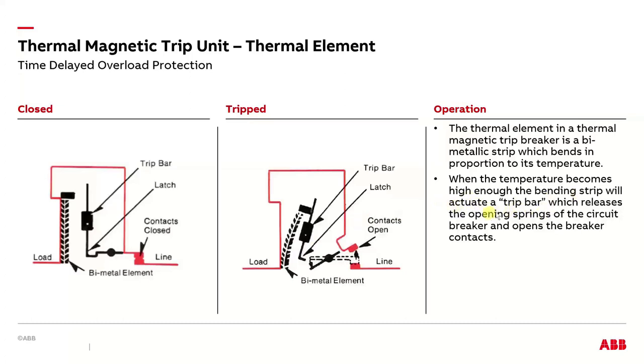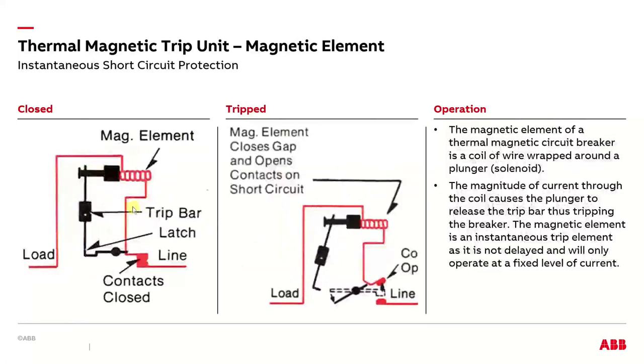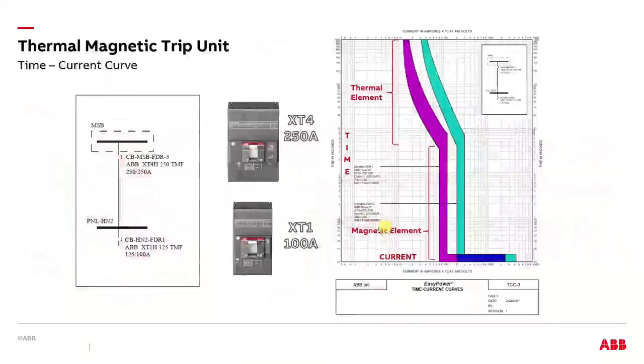Let's see here. Yeah, this just explains it. Bending bimetallic strip, trip bar, open contacts. The magnetic portion is a coil, and once the coil gets enough current flowing through it, it'll be able to pull in a plunger, which throws the latch. So very simple, but there's no time delay on it. It's either open or closed. There's no middle ground. And that's just an explanation of what I said here. So plunger, simple mechanism, and that's it. That's the trip unit of a thermomagnetic breaker.